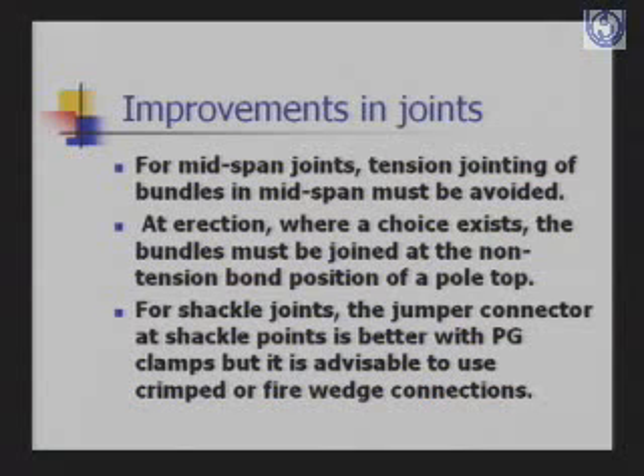The other improvements are that for mid-span joints, tension jointing of bundles in mid-span must be avoided. At erection where a choice exists, the bundles must be joined at the non-tension bond position of a pole top. For shackle joints, the jumper connector at shackle joints is better with PG clamps, but it is advisable to use crimped or fire wedge connections.